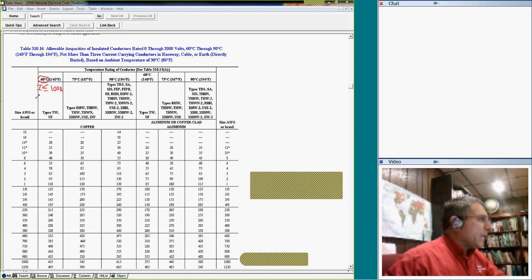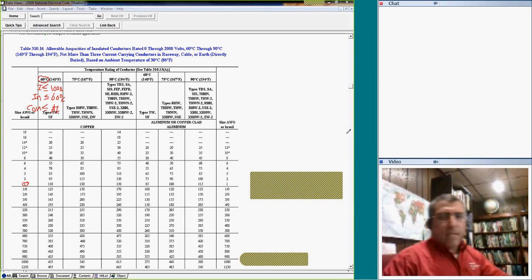Number two, the insulation: if your insulation is rated equal or less than the 60-degree column, this is degrees Celsius, you have to use the 60-degree column. Okay? And the last one, if your conductor is equal or less than number 1, right in here. If your conductor is equal or less than number 1. Any question about these rules?